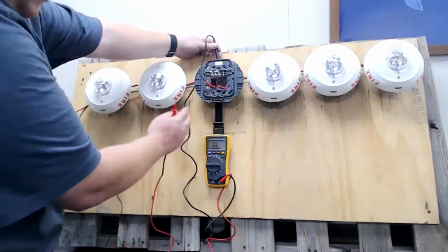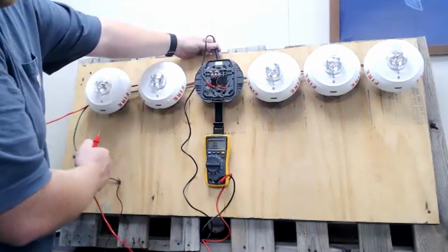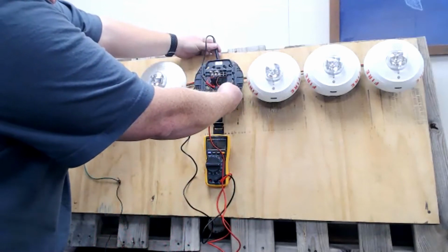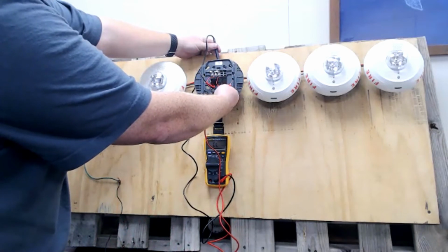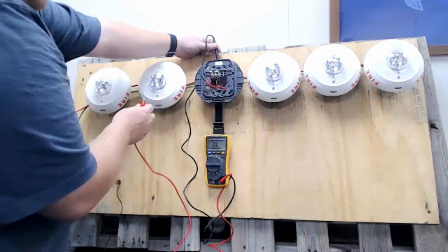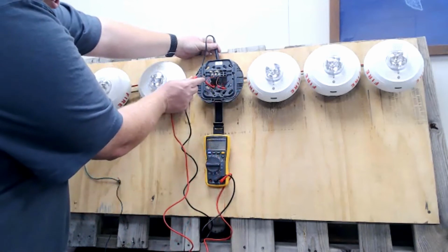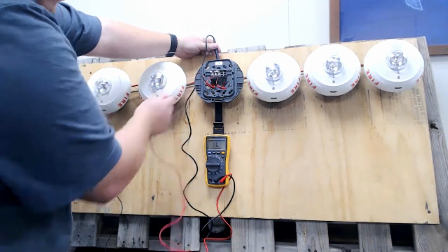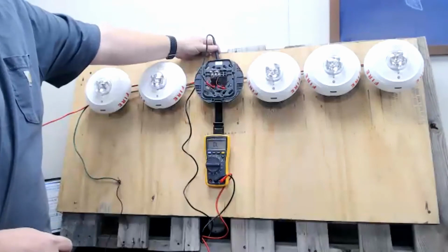So first I'm going to try to identify which half of my circuit my ground fault is on. Touching the one on the right: completely open line, no connection at all to the ground. Check the circuit on my left, and I see it's 0.3. So that number did go down, 0.2 ohms, 0.1 ohms. I have a very, very solid connection to ground right here.